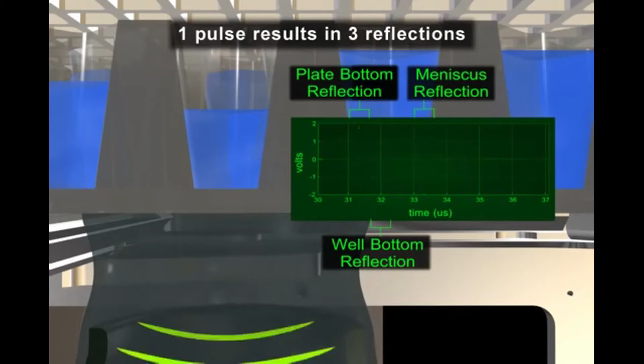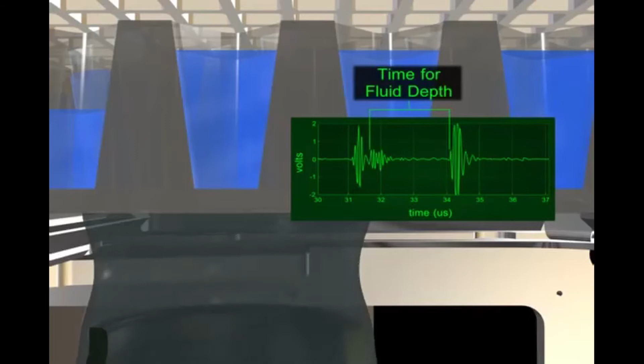The Echo uses the amplitude of the reflected sound to calculate the level of hydration of DMSO if this solvent is used in the source, and the delay of the final reflection to calculate the depth of the fluid in the well. A well filled to a greater depth requires a longer time for the reflection to return from the surface. The fluid in each well is analyzed, as shown here in slow motion.